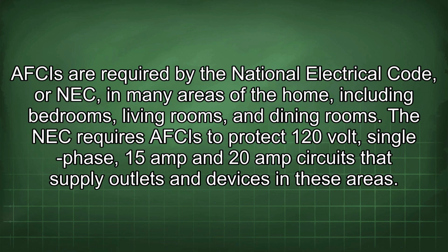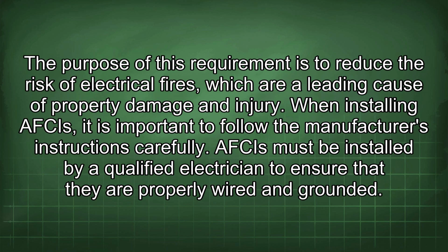AFCIs are required by the National Electrical Code, or NEC, in many areas of the home, including bedrooms, living rooms, and dining rooms. The NEC requires AFCIs to protect 120-volt single-phase, 15 amp and 20 amp circuits that supply outlets and devices in these areas. The purpose of this requirement is to reduce the risk of electrical fires, which are a leading cause of property damage and injury. When installing AFCIs, it is important to follow the manufacturer's instructions carefully.